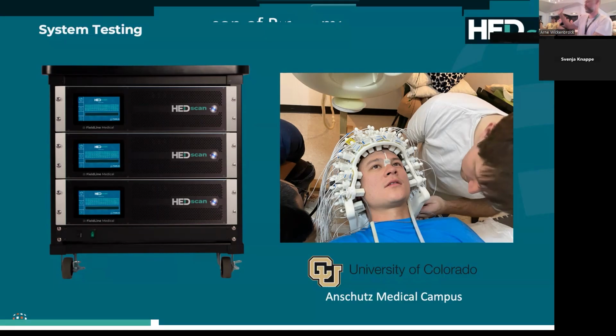All right, so there's a lot of questions. Each of these sensors sits in this translating spoke, and each sensor has a cable. There are no optical fibers. The laser is on the sensor itself. The laser power is about 250 microwatts. That's the laser power we get out of these lasers.